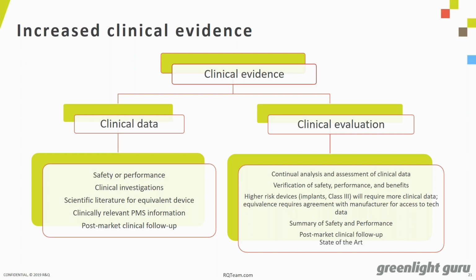One of the big changes under this new paradigm is that equivalence arguments are going to be harder to make, and in a lot of cases are no longer going to be accepted. For example, there are not only requirements for explicit comparisons between devices that have to be made for equivalence, but manufacturers of Class 3 and implantable devices have to have an agreement in place with the manufacturer of the equivalent device, granting them access to all the technical documentation. Otherwise, clinical data is going to be required on the device itself.